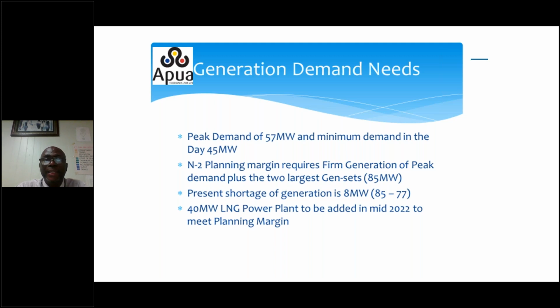And it's not so much to take care of energy, but to really look at the demand situation, as I mentioned in the N-2 planning margin. So we're presently trying to install a 40 megawatt LNG power plant. Why LNG? Well, first we thought of solar and wind with battery combination, but for the purpose for which we need the generation, it's mainly demand, firm, dispatchable demand we're requiring right now. We definitely look for the cleanest form of fossil fuel. And we also know an LNG power plant can respond to frequency variation quite a bit. Next slide, please.